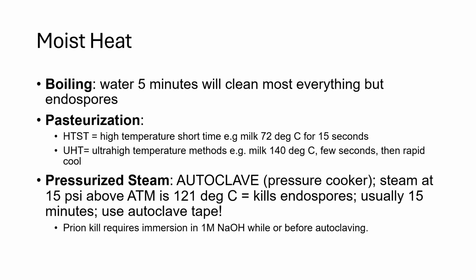Pressurized steam, the autoclave, is like your standard instrument in any lab setting or a medical setting that needs sterile equipment. Things need to be able to survive increased pressure and increased temperature, but glass and steel do just fine, and many plastics will as well, as long as you know that they're the type of plastic to do that. So steam at 15 psi, which is a whole extra atmosphere, and 121 degrees Celsius. This will take out endospores, and we usually autoclave things for about 15 minutes.